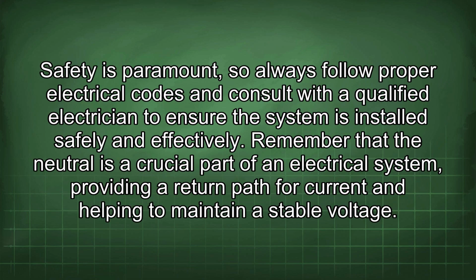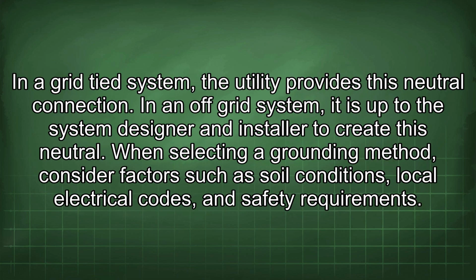Safety is paramount, so always follow proper electrical codes and consult with a qualified electrician to ensure the system is installed safely and effectively. Remember that the neutral is a crucial part of an electrical system, providing a return path for current and helping to maintain a stable voltage. In a grid-tied system, the utility provides this neutral connection. In an off-grid system, it is up to the system designer and installer to create this neutral. When selecting a grounding method, consider factors such as soil conditions, local electrical codes, and safety requirements.